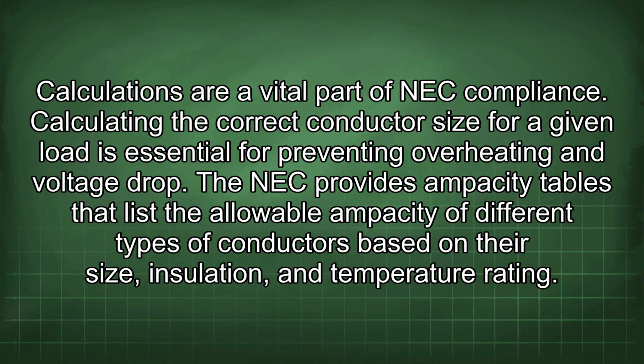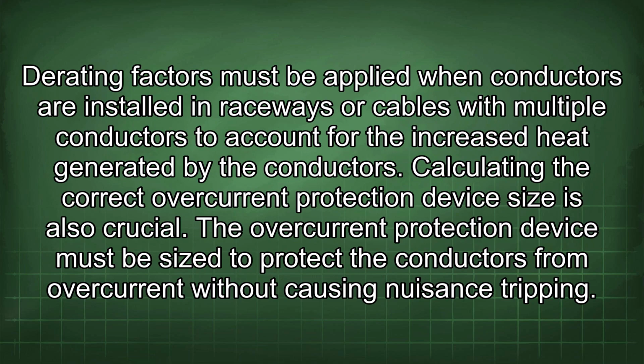Calculations are a vital part of NEC compliance. Calculating the correct conductor size for a given load is essential for preventing overheating and voltage drop. The NEC provides ampacity tables that list the allowable ampacity of different types of conductors based on their size, insulation, and temperature rating. Derating factors must be applied when conductors are installed in raceways or cables with multiple conductors to account for the increased heat generated by the conductors.